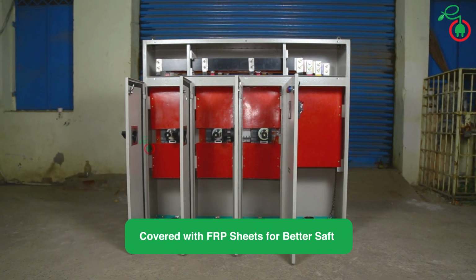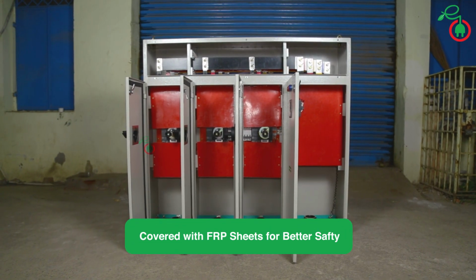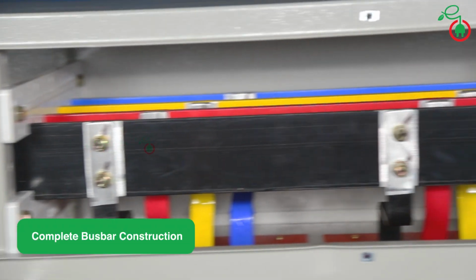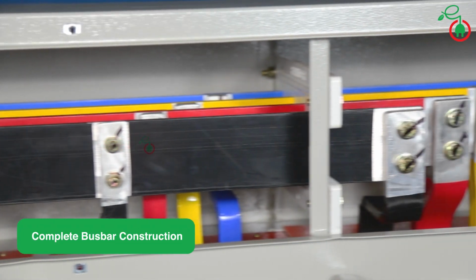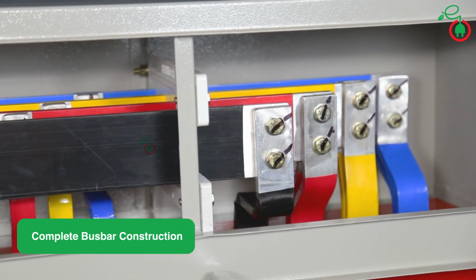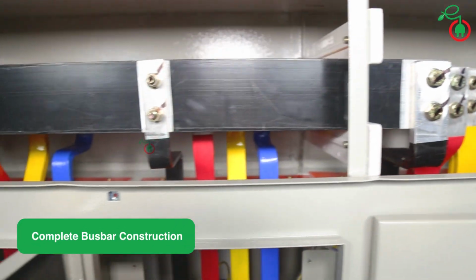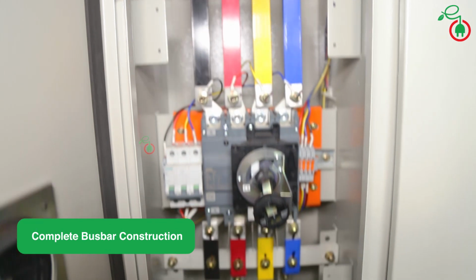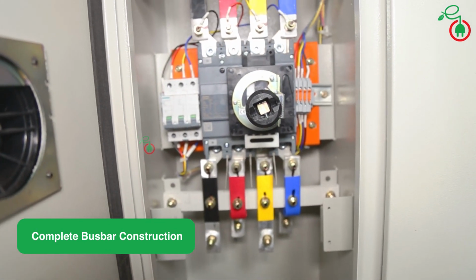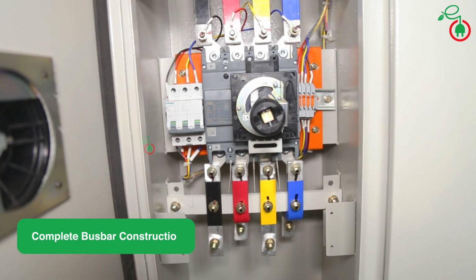The panel is completely shrouded by FRP sheets for better safety. So in this panel, except your cable, everything is busbar. No wires are used to transmit the power. When we construct the panel with complete busbar, the reliability, the efficiency, and the life of the panel will improve a lot.